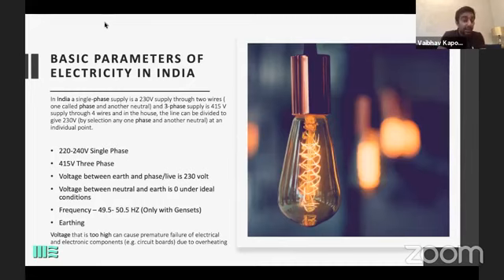There is one more thing with the genset run, which is the frequency, the cycles of the genset. So if the frequency is anywhere between 49.5 to 50.5, that means your electricity is good to go and you can switch it on. If these parameters are not right, you should never switch on the electricity, because something is going to go wrong.